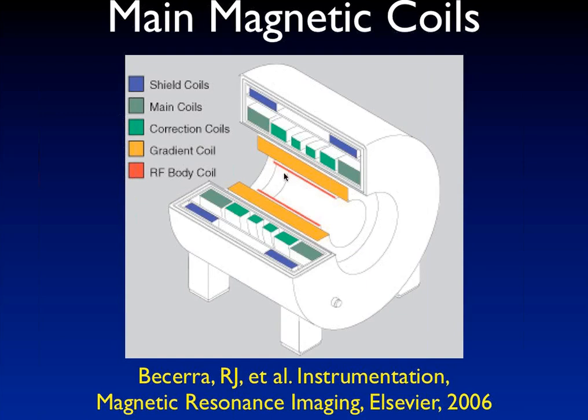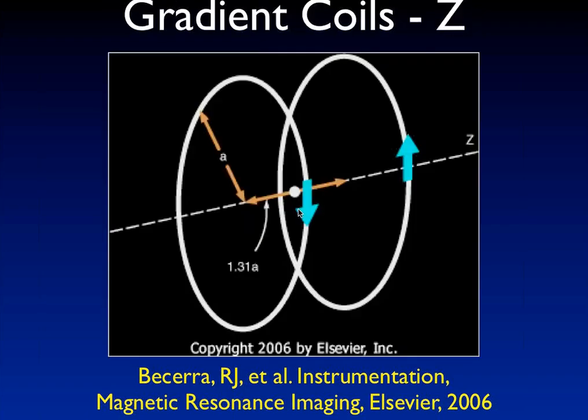This diagram shows what the coil arrangement looks like. The shielding coils are at either end on the outside to reduce the fringe field. The main coils are in the center with correction coils throughout the center portion of the magnet, current flowing in one direction. The shielding coils carry current in the opposite direction to cancel out the peripheral field. There are more windings at the periphery to achieve a uniform field, with gradient coils in the center and receiver coils closest to the patient.